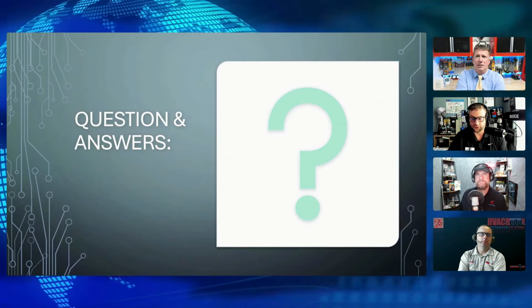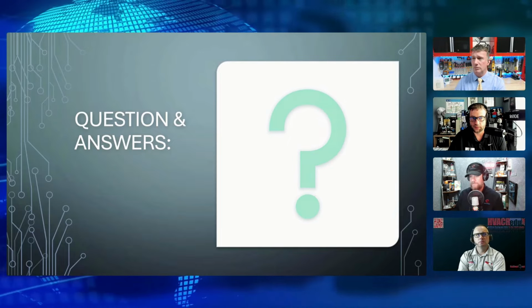Chillers. Yeah, chillers. There's a gentleman that I know, I keep bringing up Alaska, because this guy at Pro Refrigeration installed a CO2 chiller. And because CO2 creates so much heat as far as enthalpy when it's running in the transcritical state, even though in Alaska they really don't need to run it that high, they do, because they were able to reduce the amount of liquid propane, I think by 91 liters or something like that, because it's a dairy, right? So you're basically refrigerating the product for that process, but then they need heat for heating up the milk and for pasteurization, hot water, cleaning, potable water. So it's almost a zero net gain, right?